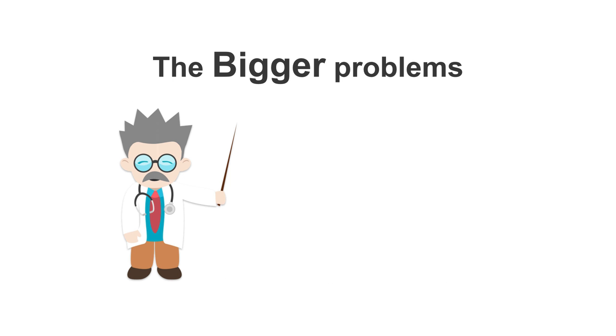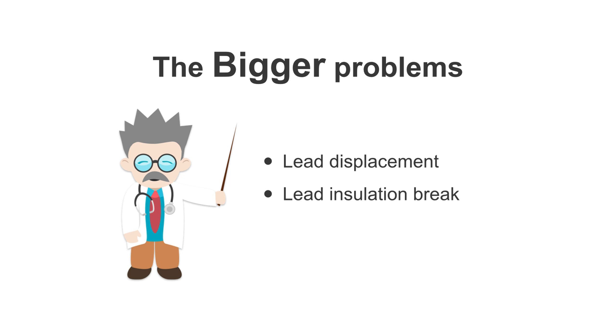However, it can be indicative of bigger problems that aren't so easy to solve. This includes lead displacement, lead insulation break, or a lead fracture.